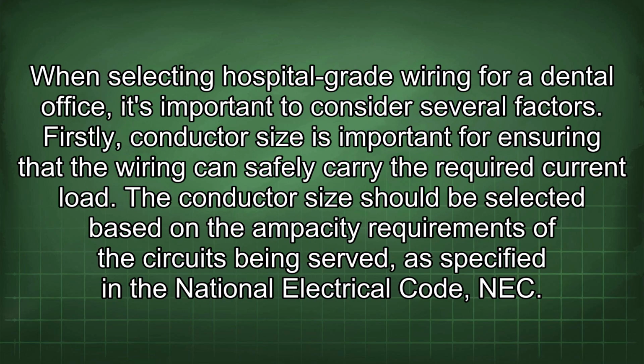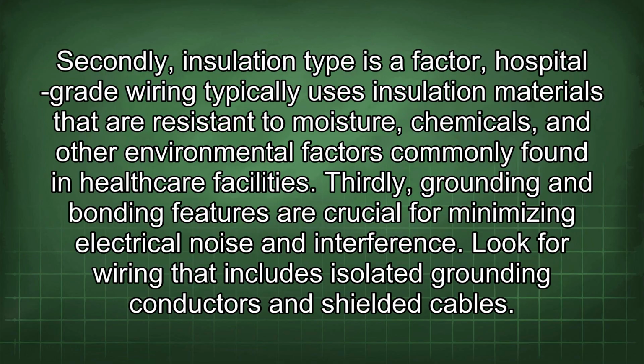When selecting hospital-grade wiring for a dental office, it's important to consider several factors. Firstly, conductor size is important for ensuring that the wiring can safely carry the required current load. The conductor size should be selected based on the ampacity requirements of the circuits being served, as specified in the National Electrical Code (NEC).